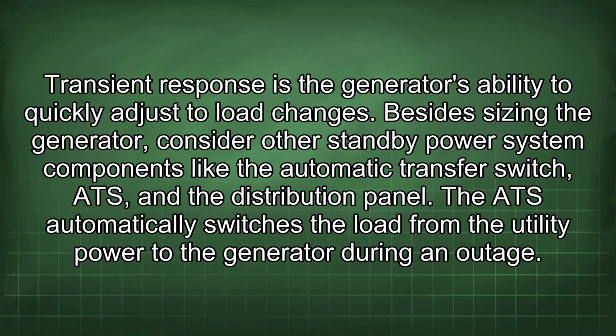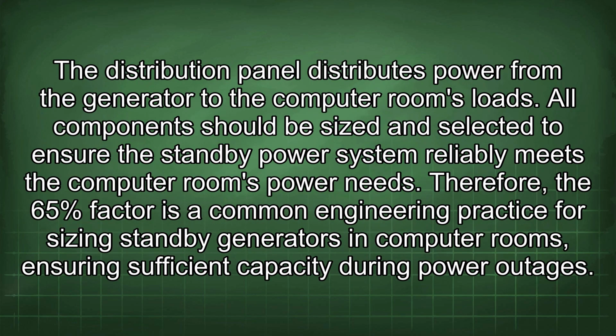Besides sizing the generator, consider other standby power system components like the automatic transfer switch, ATS, and the distribution panel. The ATS automatically switches the load from the utility power to the generator during an outage. The distribution panel distributes power from the generator to the computer room's loads. All components should be sized and selected to ensure the standby power system reliably meets the computer room's power needs.